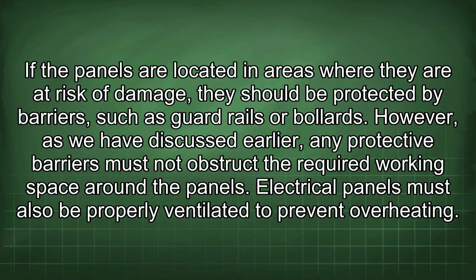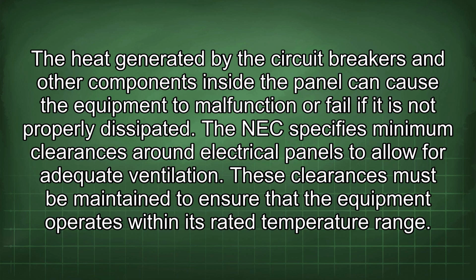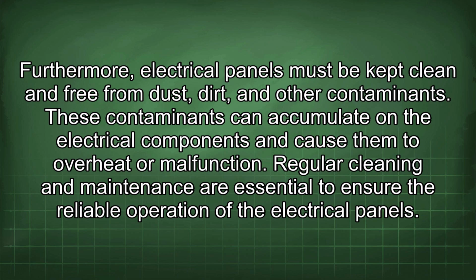Electrical panels must also be properly ventilated to prevent overheating. The heat generated by the circuit breakers and other components inside the panel can cause the equipment to malfunction or fail if it is not properly dissipated. The NEC specifies minimum clearances around electrical panels to allow for adequate ventilation. These clearances must be maintained to ensure that the equipment operates within its rated temperature range. Furthermore, electrical panels must be kept clean and free from dust, dirt, and other contaminants. These contaminants can accumulate on the electrical components and cause them to overheat or malfunction. Regular cleaning and maintenance are essential to ensure the reliable operation of the electrical panels.